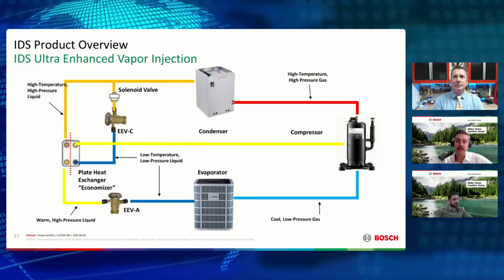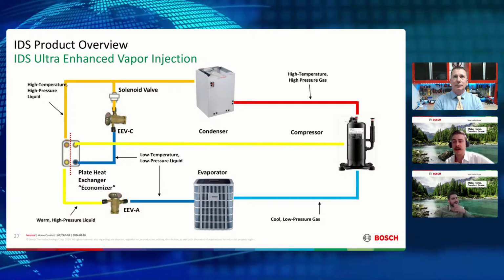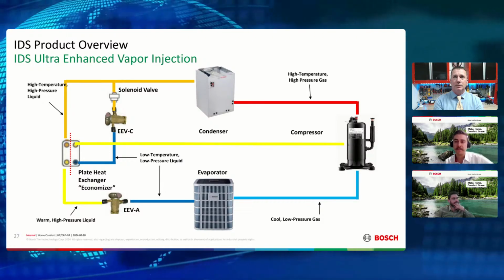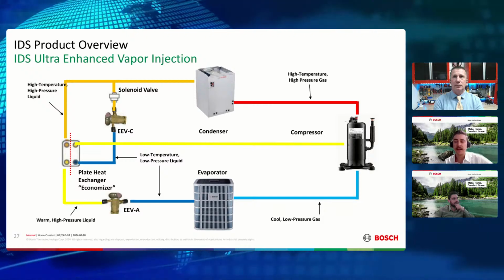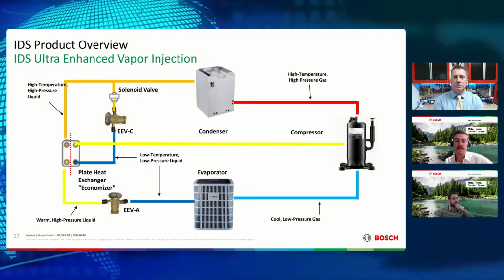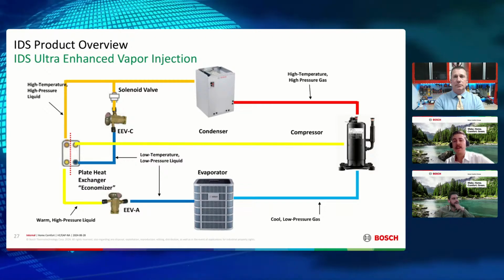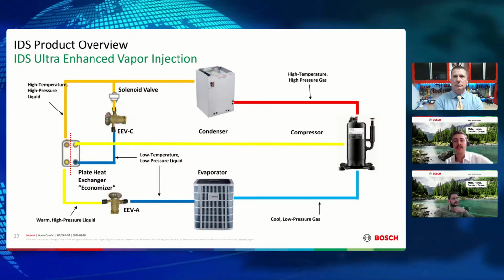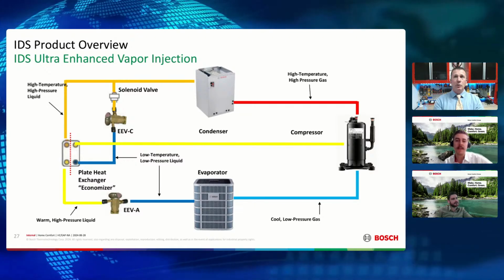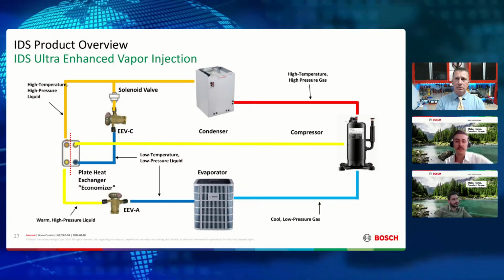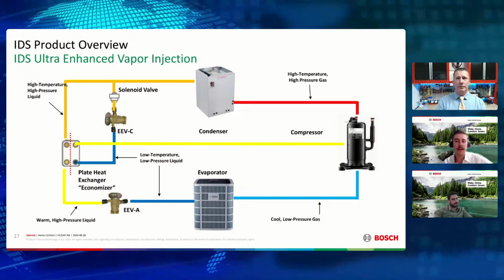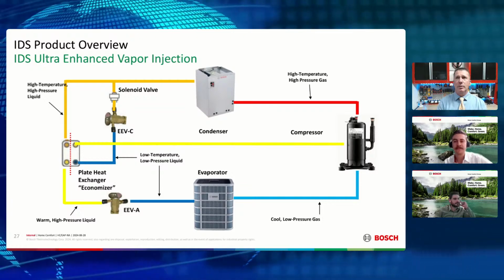This is also going to be a special vapor injection compressor with 2 inlets and 1 outlet. Your main flow is going to have a full-size accumulator, but your injection inlet is also going to have a mini accumulator. That's so when the system starts from rest, it's always going to draw gas - no pulling liquid back into our pump.